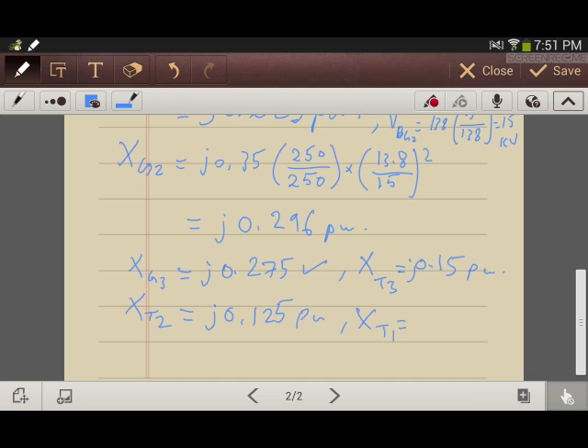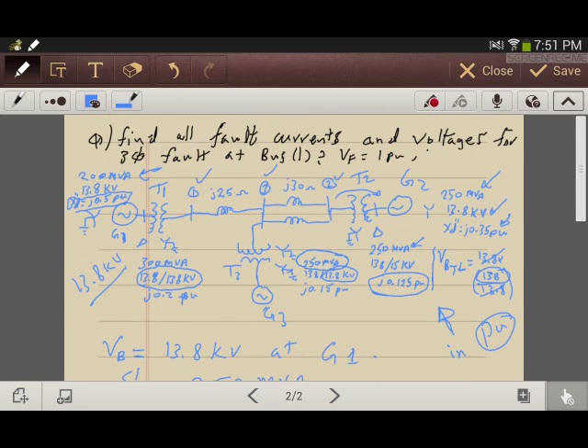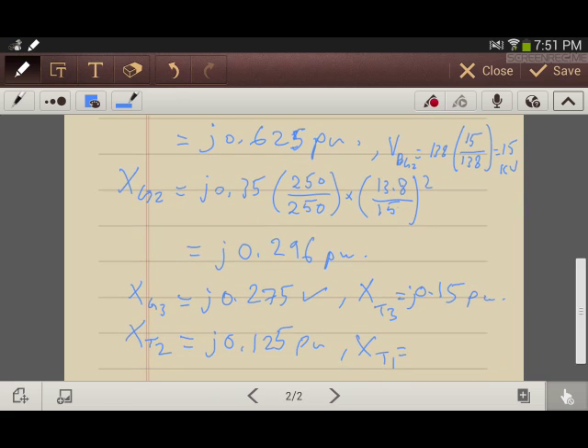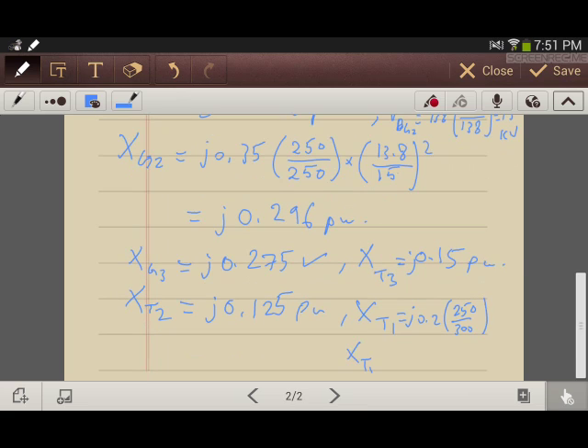For transformer number one, the rated MVA is 300 MVA, so the per-unit reactance will change. It will be j0.2 multiplied by (250/300), giving transformer one reactance equal to j0.167 per unit. Finally, we have to find the transmission line per-unit reactance, which I will do in the next slide.